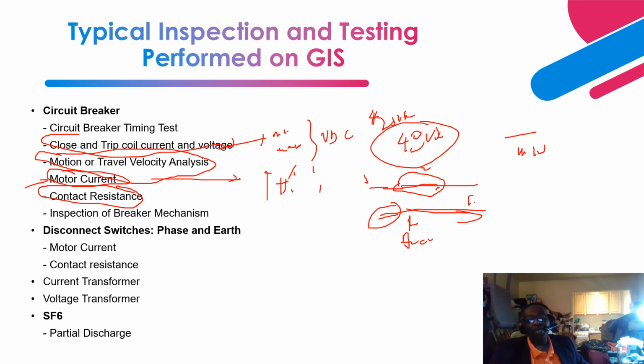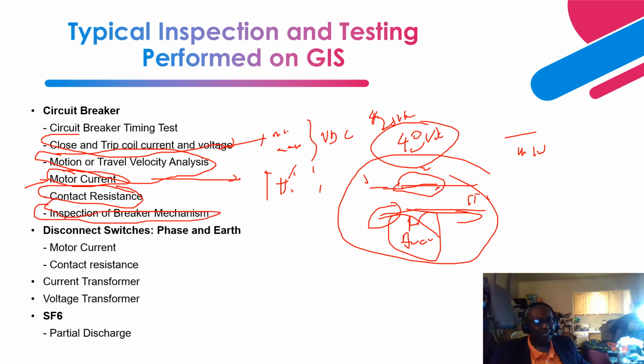And the goal of the SF6 is basically to extinguish the arc that is formed to prevent recovery of voltage. Because as you know, recovery of voltage is not ideal for the circuit breaker. Next is inspection of the breaker mechanism. Okay, so the inspection of the breaker mechanism is done. Usually that is recommended after the manufacturer will specify that inspection to be done, after a certain number of operations of the breaker mechanism, certain operations of the circuit breaker, right?